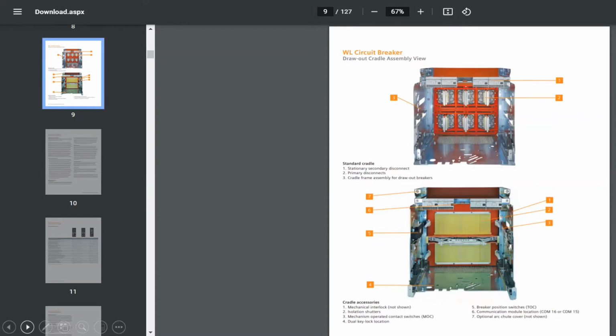When you're exercising breakers, what should you do too? Just start turning it on, turn it off. Go downstream and take the load off it. You don't want to close an 800 amp breaker onto an 800 amp full load, agreed? So go downstream, turn off the panel boards, open the big breaker, close it, and go turn on the load a little at a time. You don't want that surge of current coming in, because when I'm operating, all I'm doing is making the mechanism click in and out.